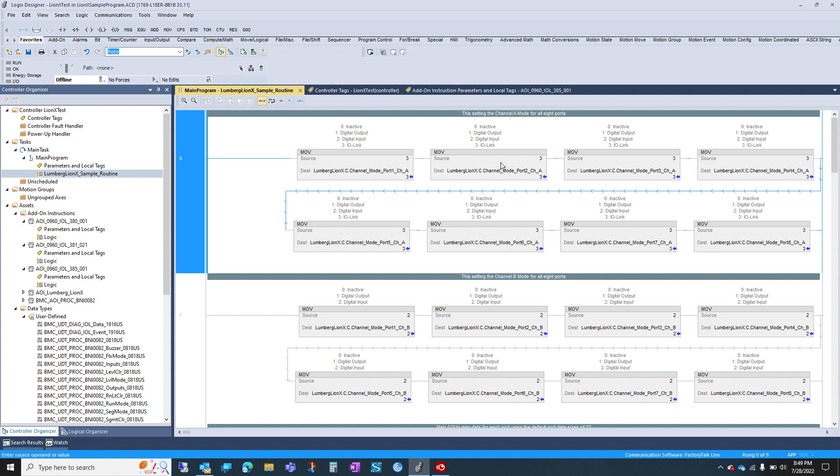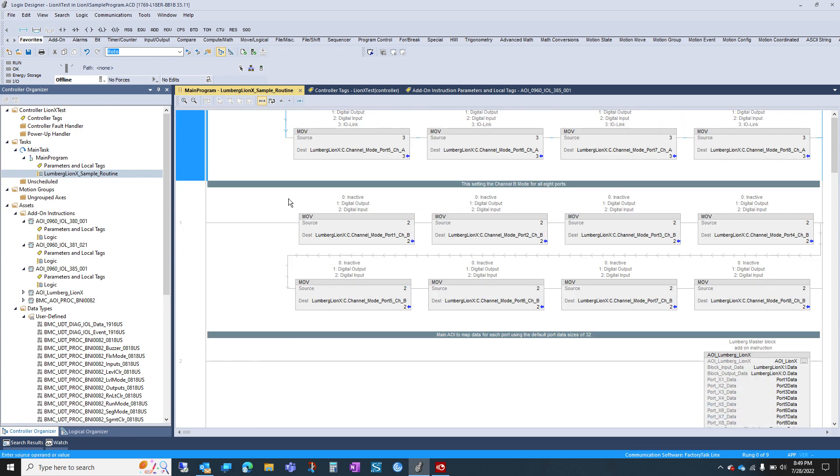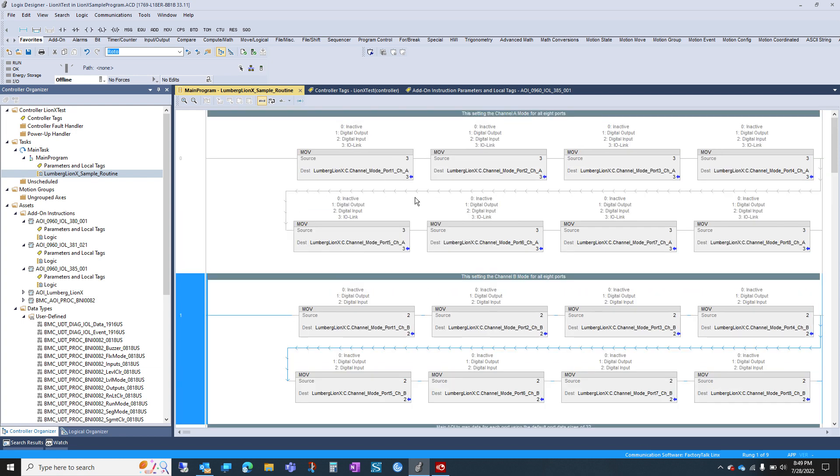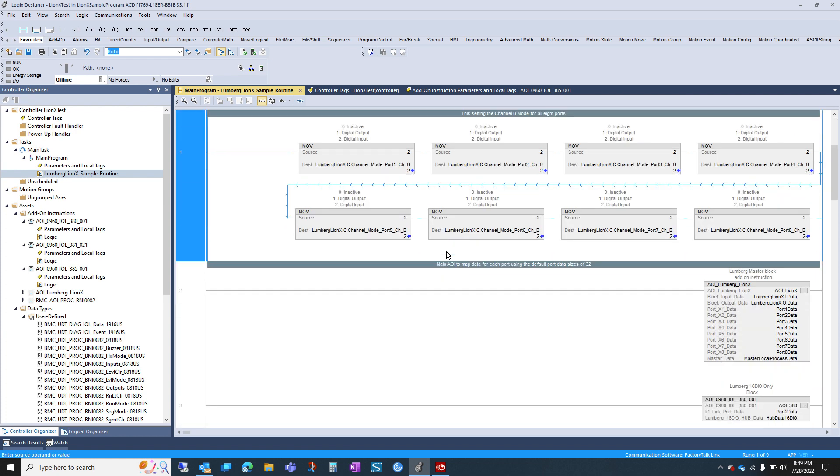By default, I believe all these ports will be set to three, but we did it here anyways just to show you what your options are between inactive, output, input, or IO-Link. And this is the A channel. On the B channel, you have the same thing. You set a 2 to be digital input, set a 1 to be digital output. If you've made any changes here, you do need to cycle power on the block before they'll take effect.